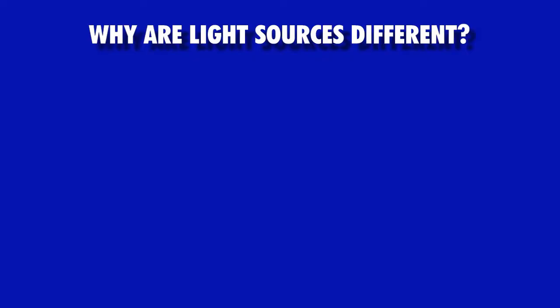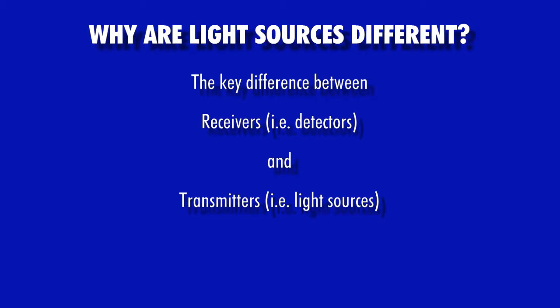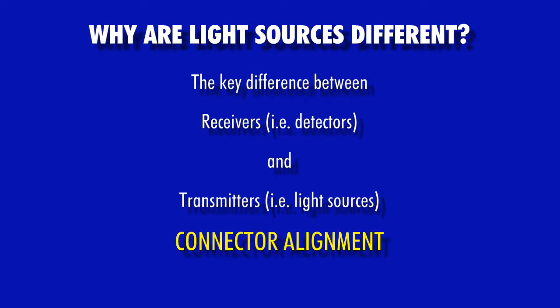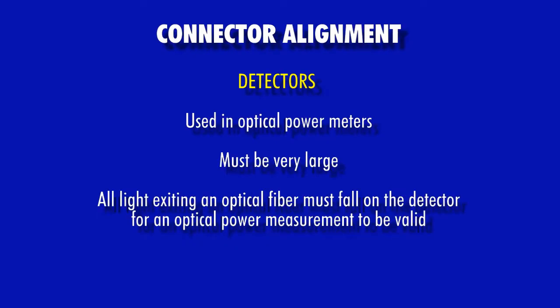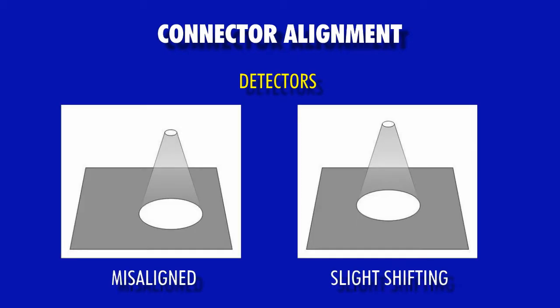Before continuing, it is important to understand the key differences between receiving equipment, in other words, detectors, and transmitting equipment, in other words, sources. This issue is connector alignment. Detectors, which are used in optical power meters, must be very large in relation to a fiber core in order to fully accept the light exiting the installed fiber link, regardless of fiber type. Thus, a connector port could be slightly misaligned or could even shift a little bit in the detector port, and this would not affect the optical power readings at all.